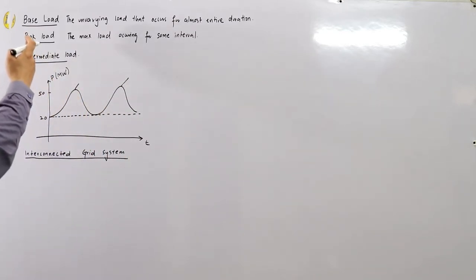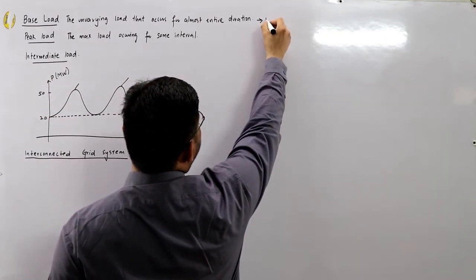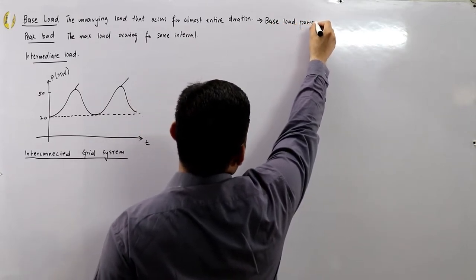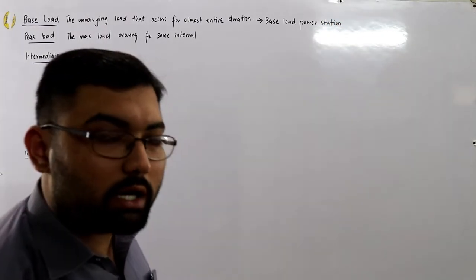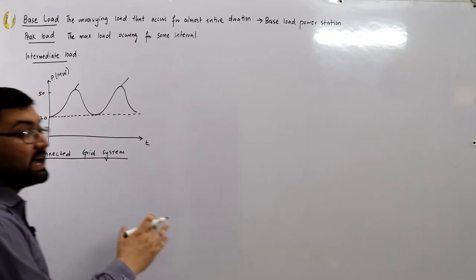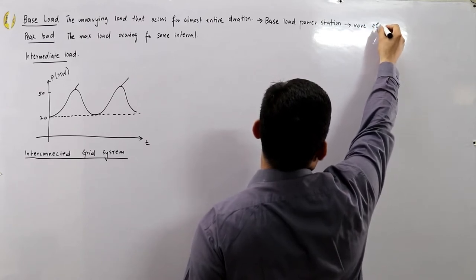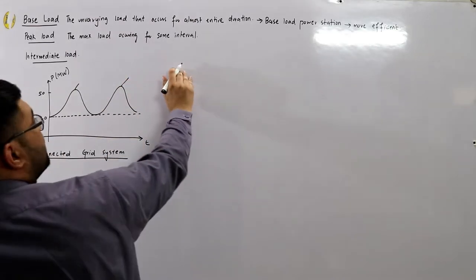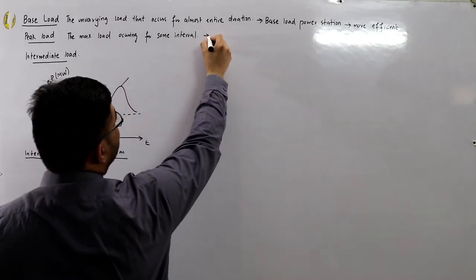The base load power station has to be efficient because it operates for more time and needs a higher working capacity. Similarly, the power station used to supply the peak load — such as 50 megawatts — is called the peak load power station, and it is relatively less efficient because it operates for only a small percent of the time.